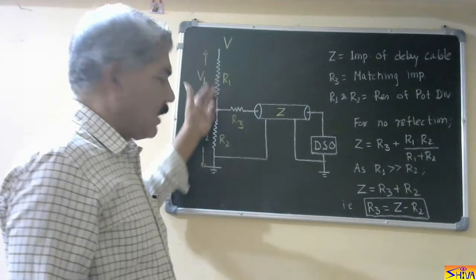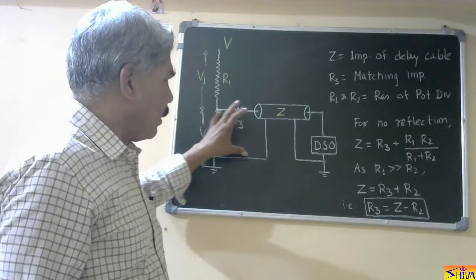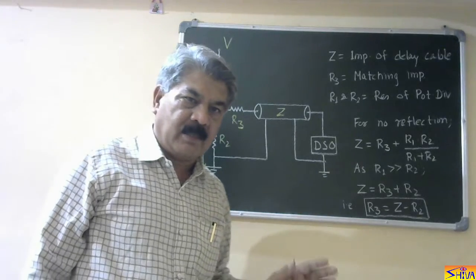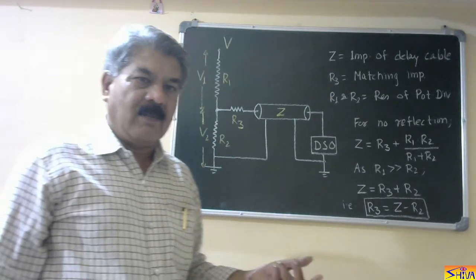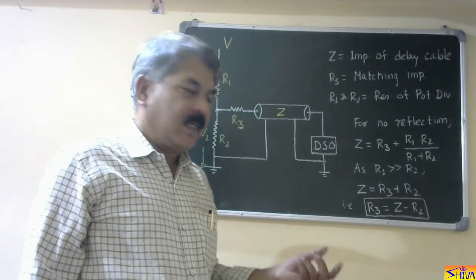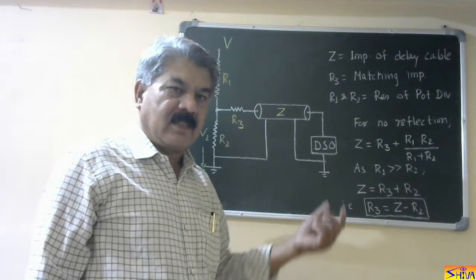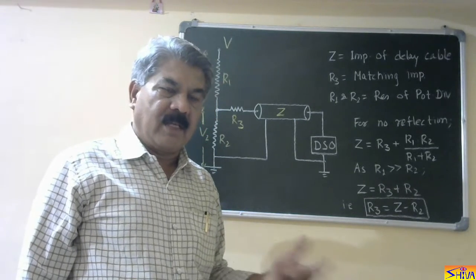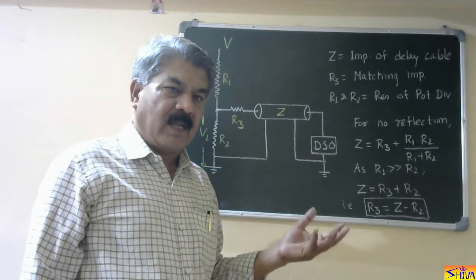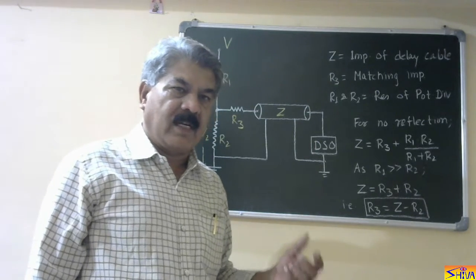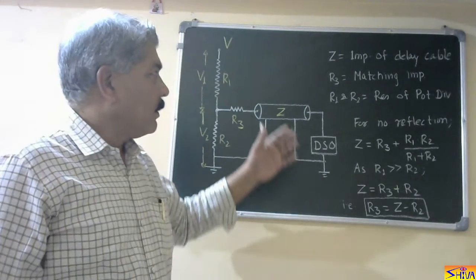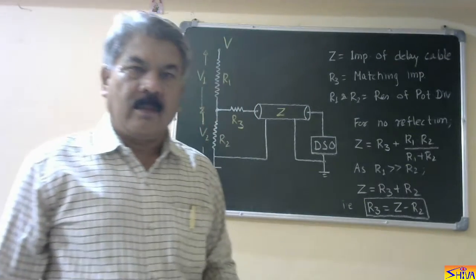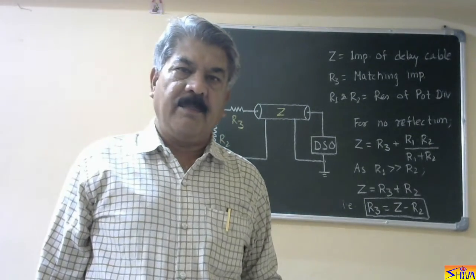Then whatever impulse voltage is coming, a sample of that will go to the digital storage oscilloscope, and the digital storage oscilloscope will record this impulse waveform. So if there is any flash over, spark over, or breakdown of the test object, the DSO will record that event also, and we can come to know the shape of the voltage wave. If there is no breakdown, and if there is flash over, we can note down the point of flash over on the chopped wave. So in this way, the impulse voltage is recorded. That is all about the measurement and recording of the impulse voltage wave.